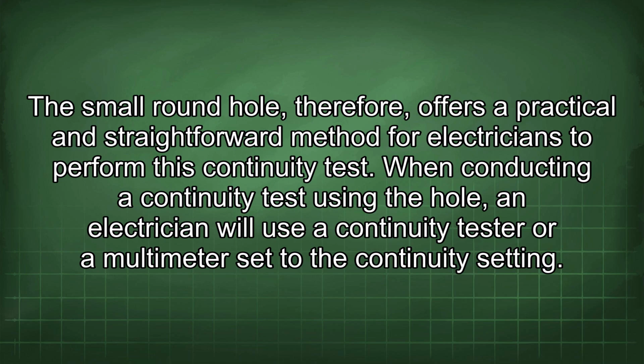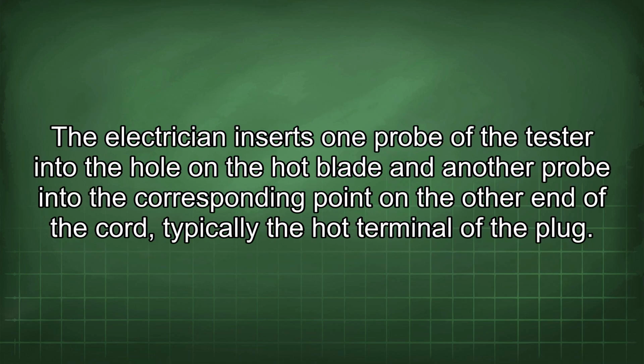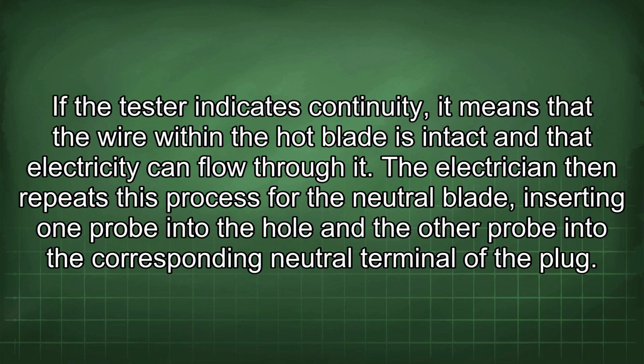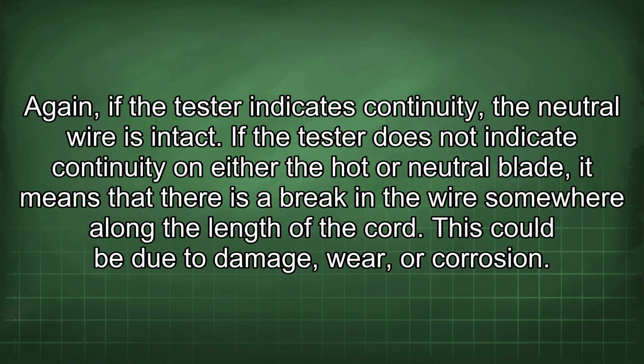When conducting a continuity test using a hole, an electrician will use a continuity tester or a multimeter set to the continuity setting. The electrician inserts one probe of the tester into the hole on the hot blade and another probe into the corresponding point on the other end of the cord, typically the hot terminal of the plug. If the tester indicates continuity, it means that the wire within the hot blade is intact and that electricity can flow through it. The electrician then repeats this process for the neutral blade, inserting one probe into the hole and the other probe into the corresponding neutral terminal of the plug. Again, if the tester indicates continuity, the neutral wire is intact.